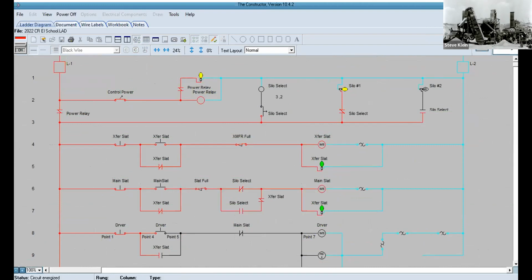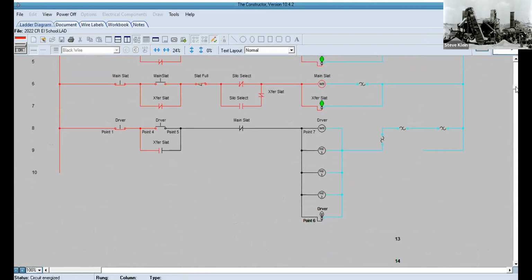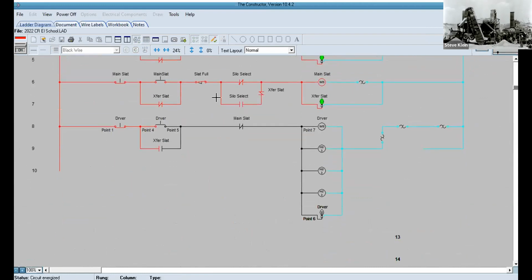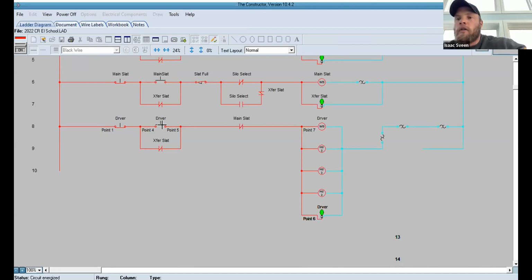Then I'll pull on down here, and let's watch these starters pull in. I'm going to hit the dryer. When I hit the dryer, you notice all 4 of them pull in, plus the light comes on. But if any one of those 3 overloads drops out, they'll all shut off.